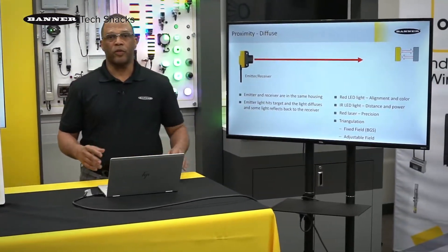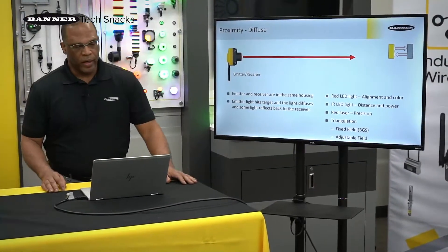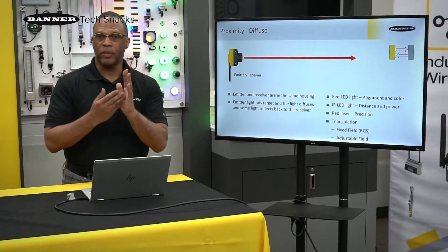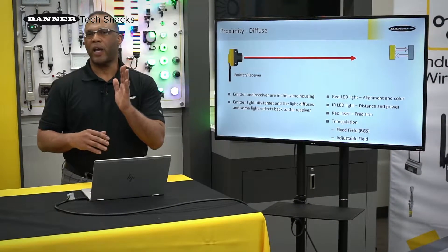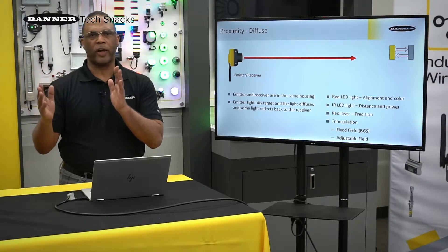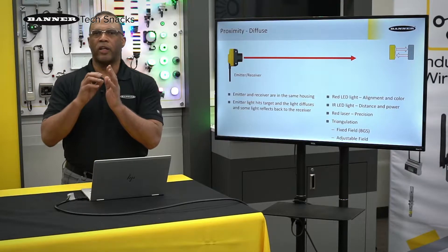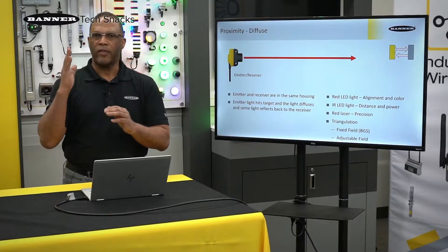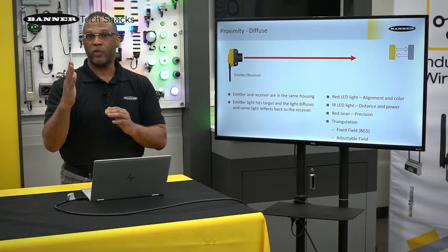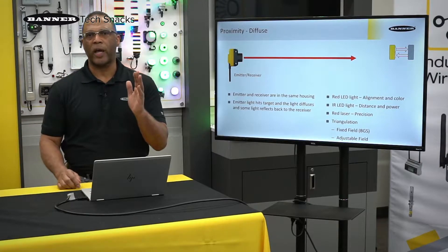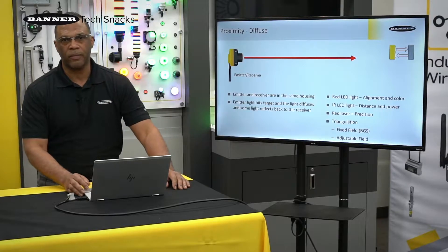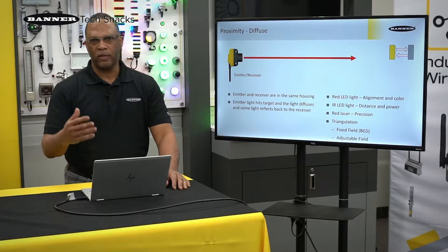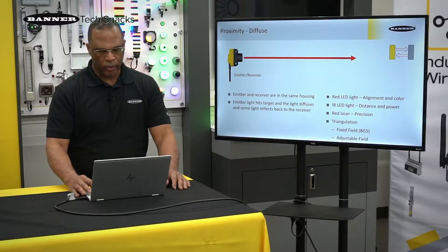We're going to start off with the diffuse mode. The diffuse mode sensor has the emitter and receiver in one housing. It doesn't need anything like a reflector or a receiver on the other side. Diffuse spreads light out, and the object it's trying to detect is what sends light back to the element. With these sensors, we use red LEDs, infrared, and laser.